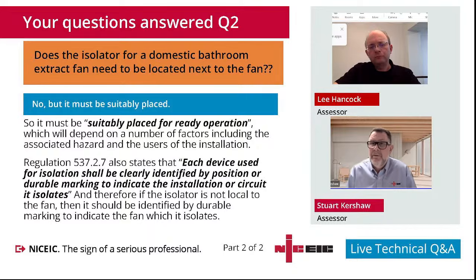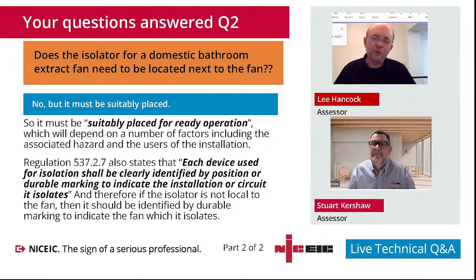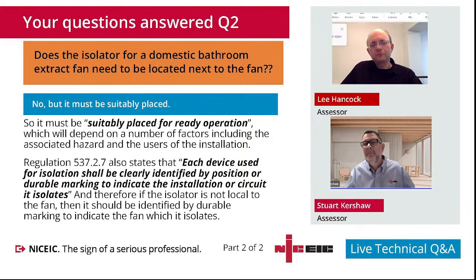Mm-hmm. Another point to make on that one, Lee, is 464.4, which is an inherent issue with some of the manufacturers of these devices, that they're not lockable. And the suitable means against inadvertent reclosure is another issue, possibly with locating them outside of or away from the extract. Yeah. I have seen a couple of extract fans where you can pop a key into the front of them, Stuart, but the amount of times I've seen these, I can probably count on one hand. We're not mentioning manufacturers' names tonight, but we've got a few that are now on board with it and are making them lockable as well. So just worthy to mention that.